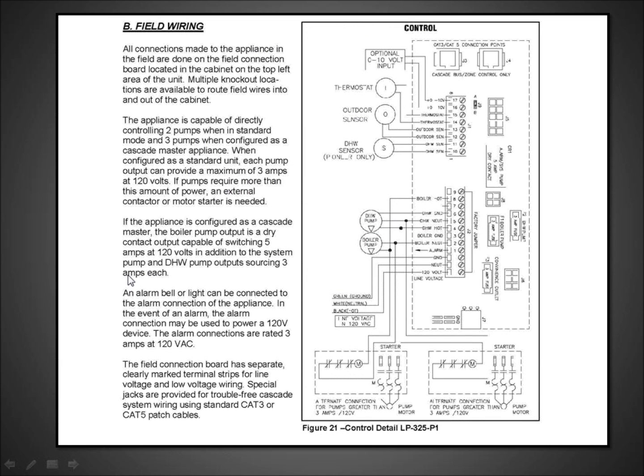We changed the wiring. One of the things we wanted to do is we added a jumper in the wiring for the Pioneer and the wiring for the VersaFlame, and there's a reason for this, which I'm going to show you in a second. So this jumper is factory installed. This jumper will come out when you're utilizing a Flame where you're doing priority, where you want to set the unit up on priority, and I'll show you how that's actually wired. But this will be a change we're making. It's starting July 1st on the Pioneer, which is new, and the manuals will reference that.